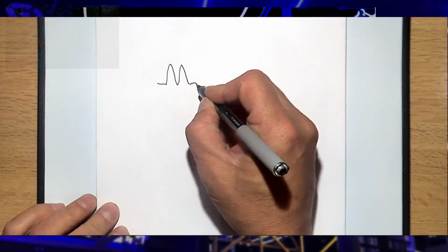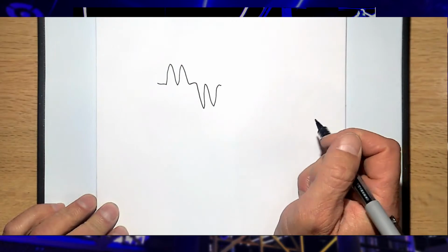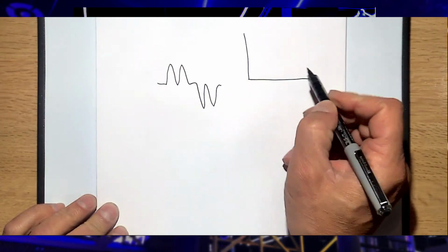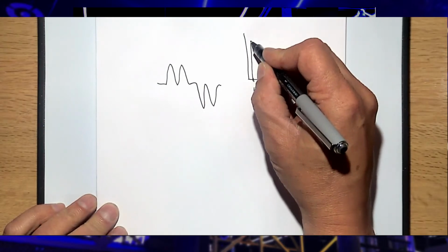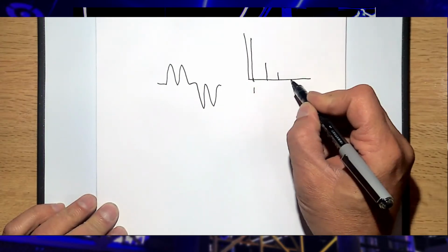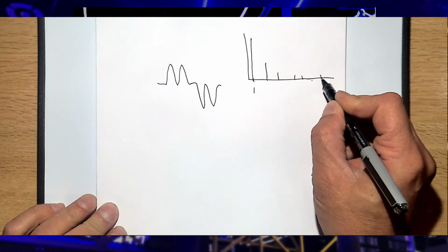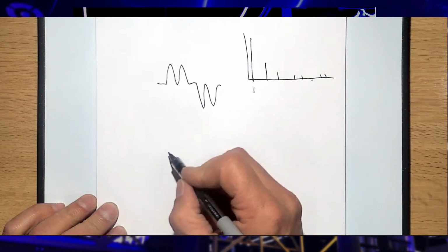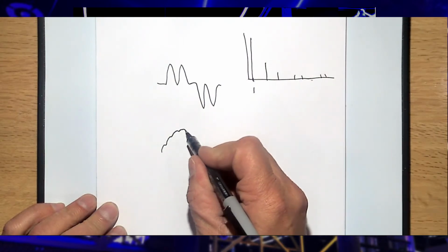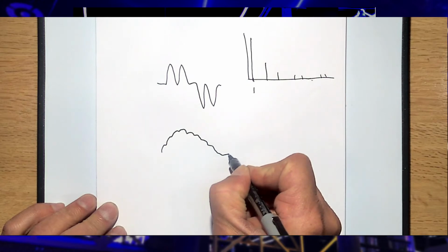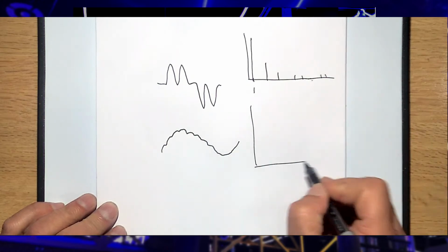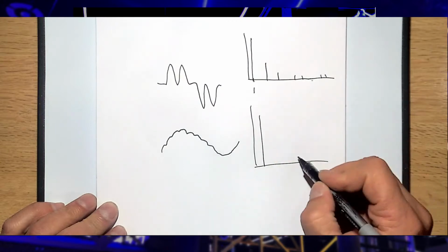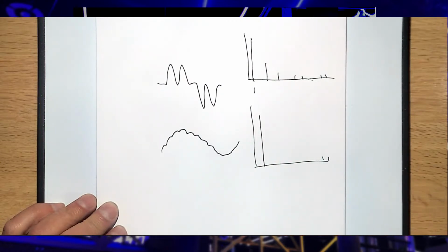It's mostly just less trouble with harmonics. A 6 pulse drive current looks like this. If you look at the frequency spectrum, you have a fundamental, the first harmonic, and then 5th and 7th, 11th and 13th, 17th and 19th harmonics, and so forth. An 18 pulse drive, literally the current has 17 little blips in it. If you look at which harmonics it has, it's the fundamental, then 17th and 19th, then 2 times that, and so forth.